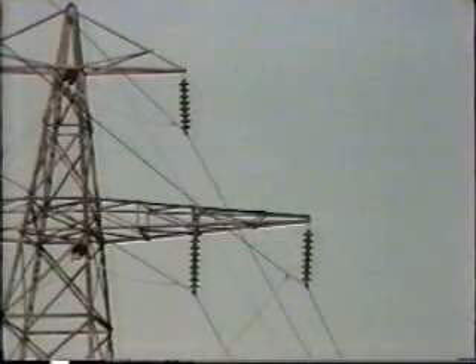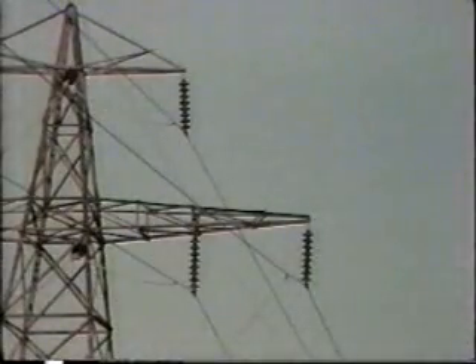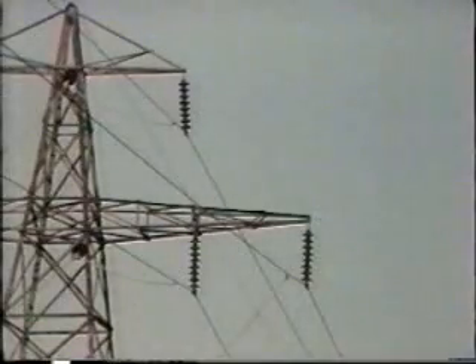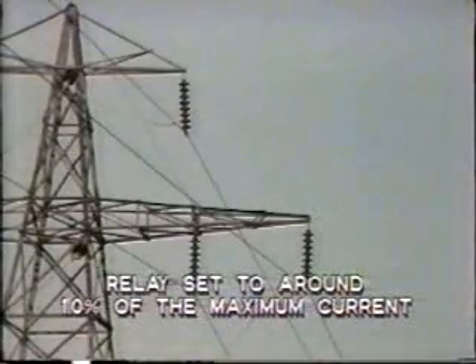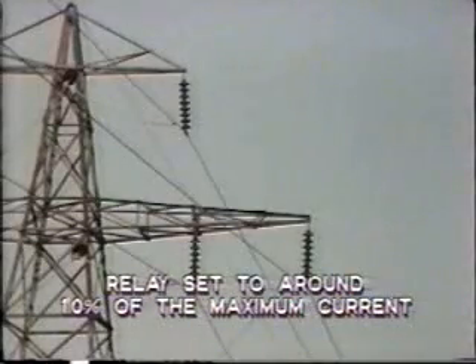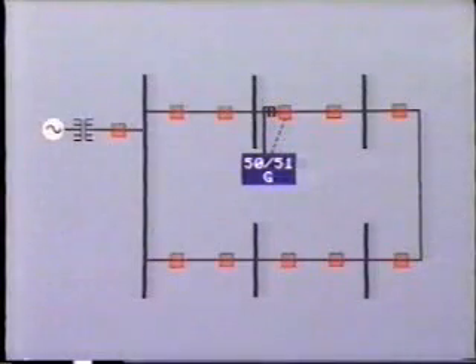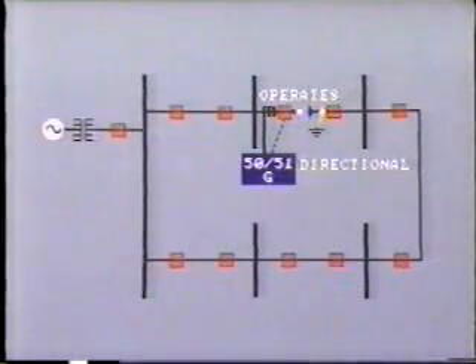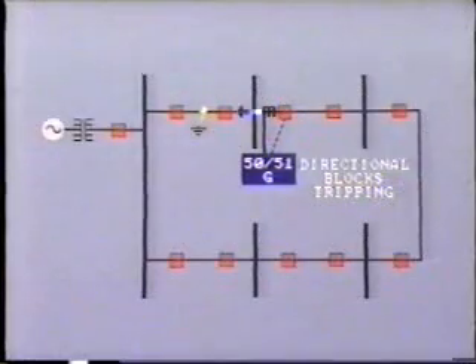The situation is different where the ground overcurrent relay is installed on sub-transmission or transmission lines. Generally, in these circuits, the loading across the three phases is balanced. Therefore, the relay can be set to a much lower pickup, usually around 10% of the maximum current. In a loop system or complex transmission system, the ground overcurrent relays are normally controlled by directional units. The relay will be allowed to operate when ground fault current is flowing into the line, but the directional element will block tripping if the fault current is flowing out of the line into the next section. This is correct. We need the local breakers to open, but the remainder of the system should remain energized and in operation.